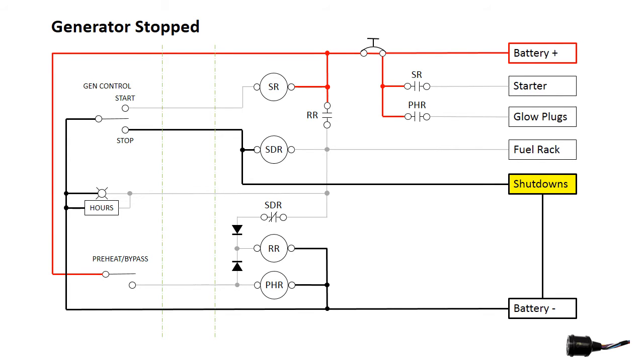Now, let's run the gen set. We begin by holding down the preheat and shutdown bypass switch. This energizes the preheat relay coil, which closes the preheat relay contacts and energizes the glow plugs.